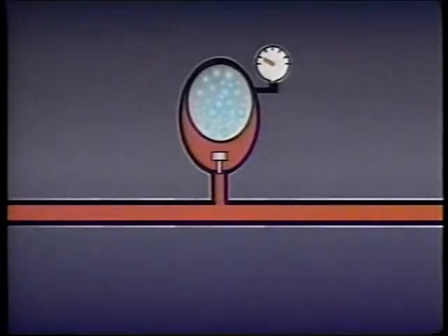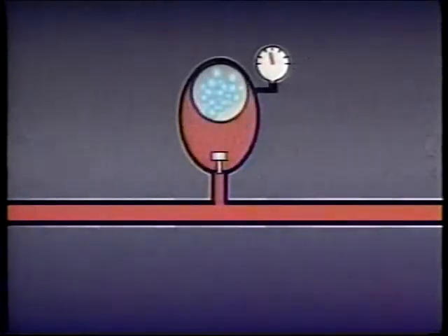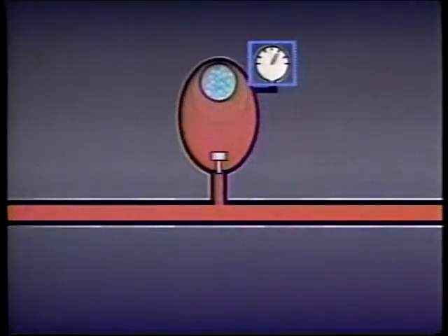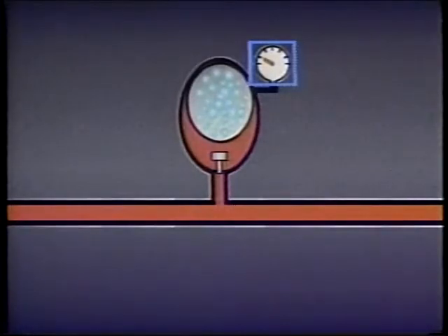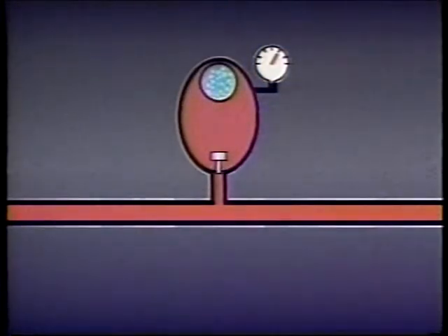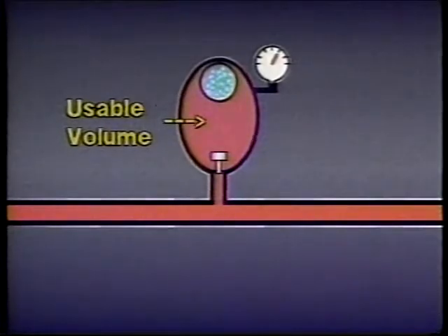After the accumulator has been pre-charged with nitrogen it is ready to be used. To develop flow or to maintain fluid pressure, the accumulator must be filled with fluid until the nitrogen pre-charge reaches a specific maximum pressure. Then as the system requires flow or pressure, the accumulator discharges fluid until the pressure of the pre-charged nitrogen drops to a specific minimum level. The volume of fluid the accumulator discharges between a maximum pressure and a minimum pressure is called the accumulator's usable volume.